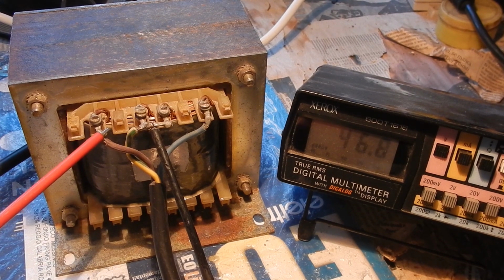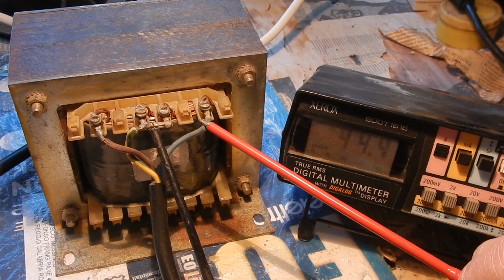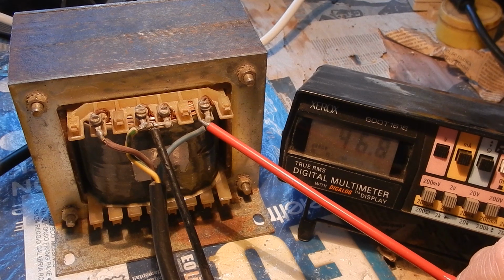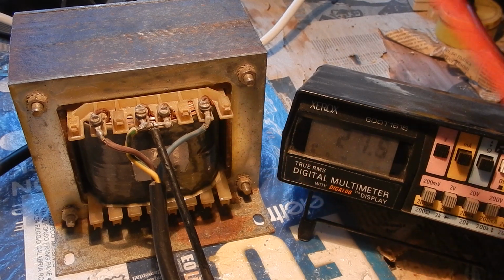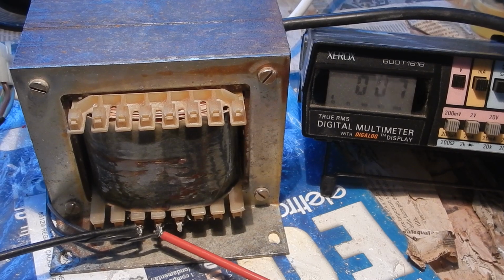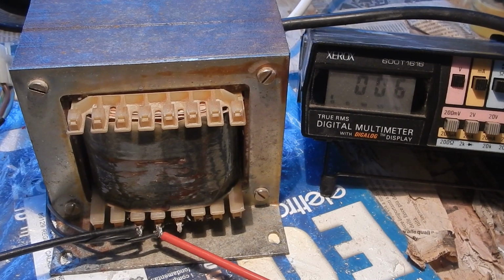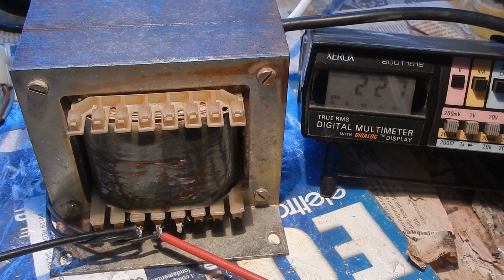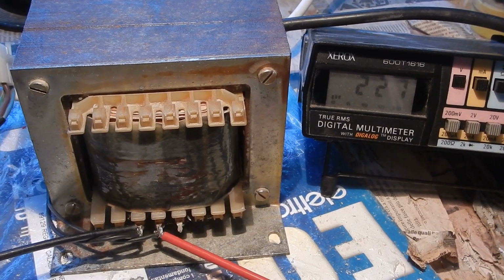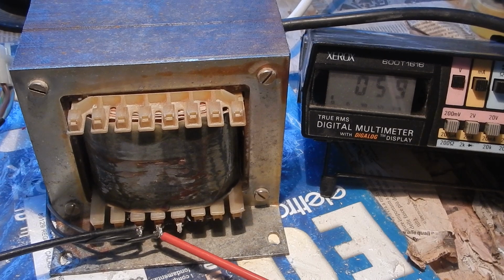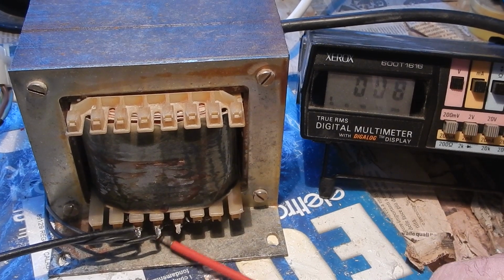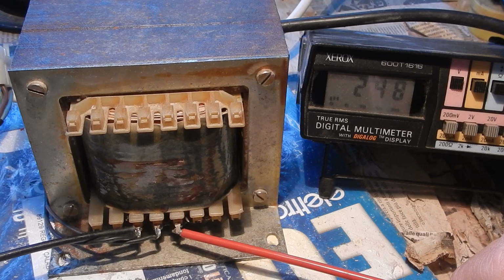Well, almost 47 volts, right at the limit I expected. The other tap obviously shows the same voltage. So let's measure the transformer primary side. At this moment the mains voltage here is 227 volts, as low as it usually gets at night. On the unconnected primary tap I can measure 248 volts, so it's probably wise to use the high voltage primary tap.